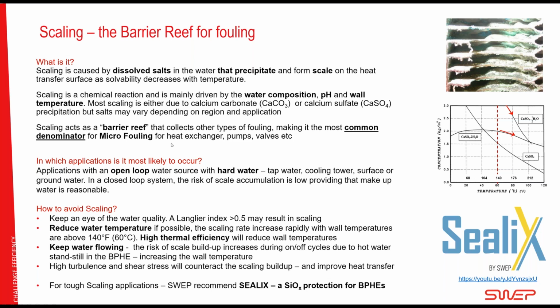I go back. What do I mean with a barrier reef? Well, scaling is, I would say, the common denominator for microfouling. It's where we see microfouling, there's typically scaling as well. They act as a couple. And the problem with scaling is that it builds up inside and captures silt, etc., that maybe normally would just pass by. So if you have a water that is prone to scaling, keep an eye on it. Keep an eye on the pressure drop over the heat exchanger, etc., because there is a higher risk that you will come into a fouling issue.